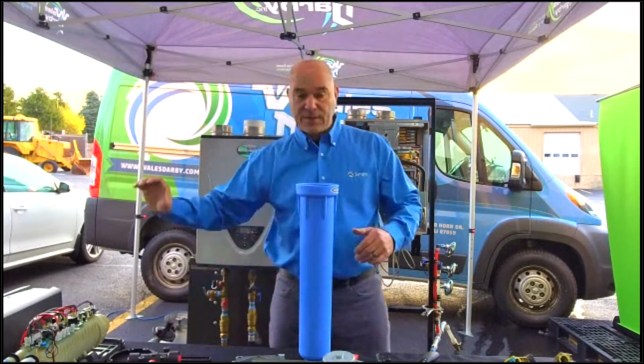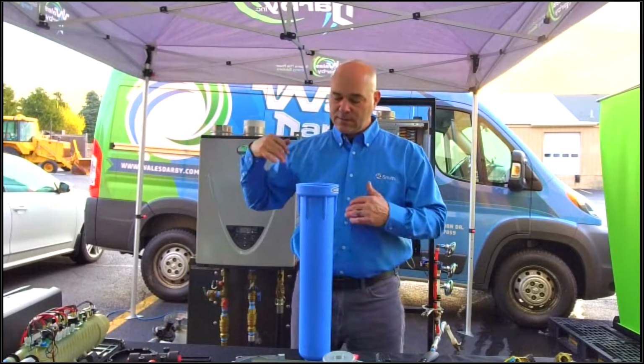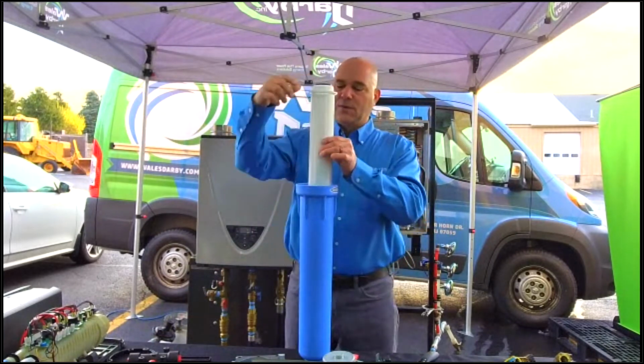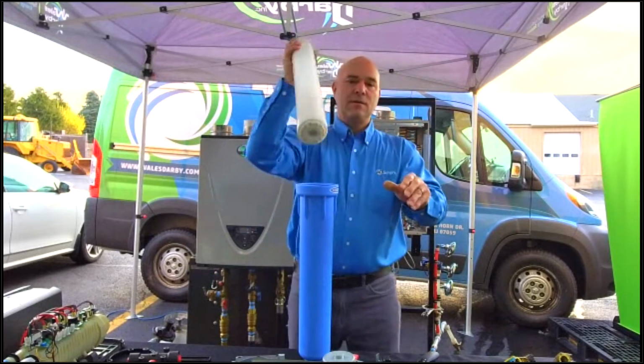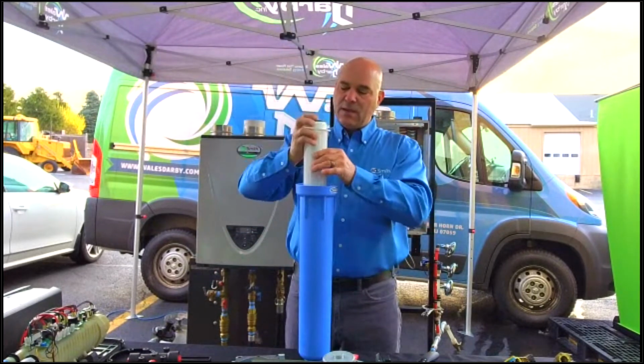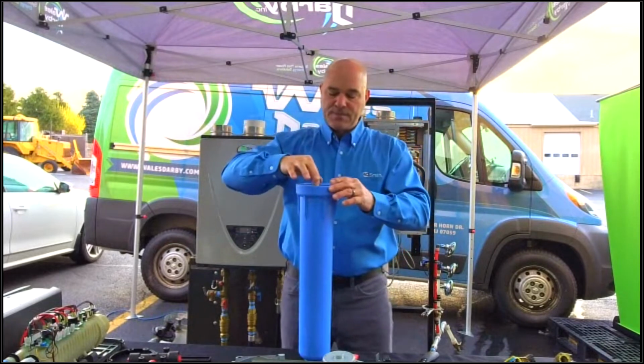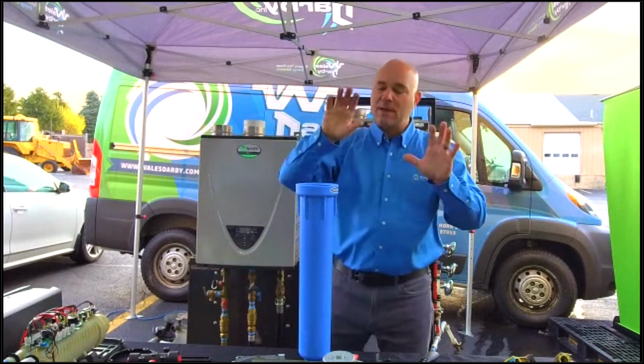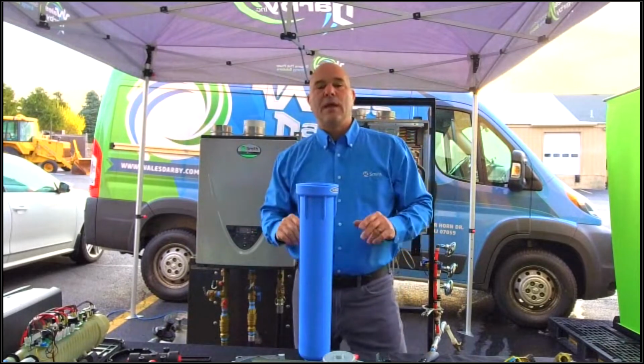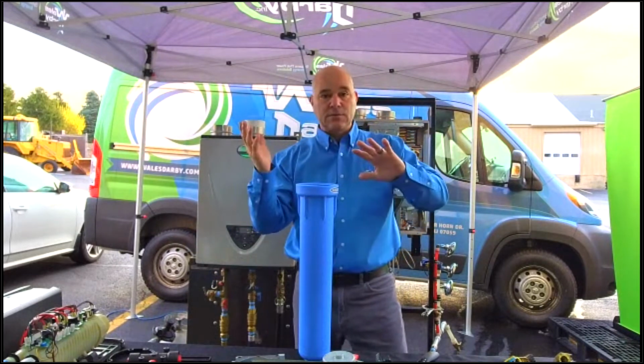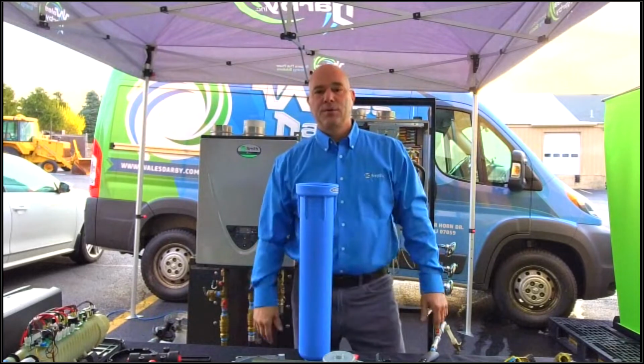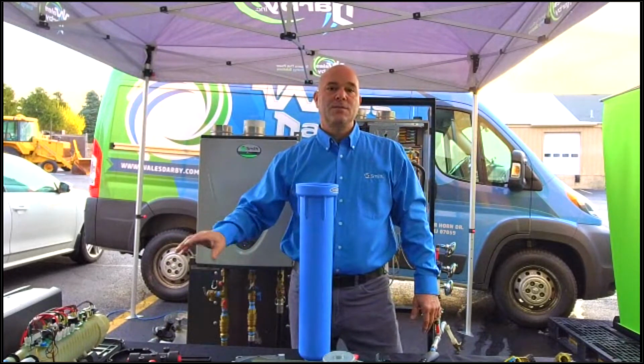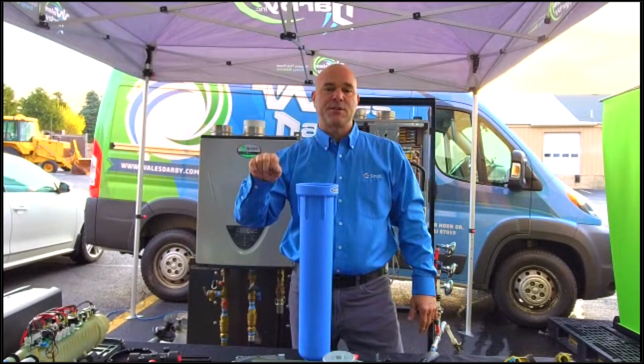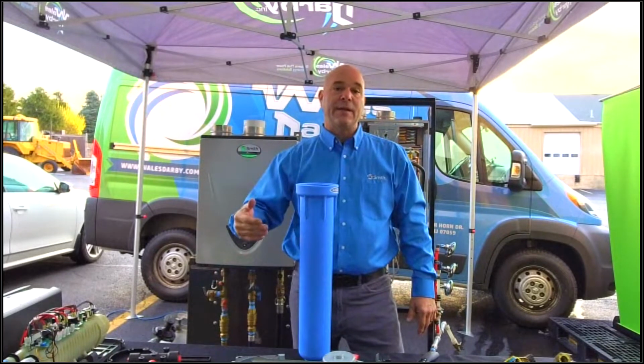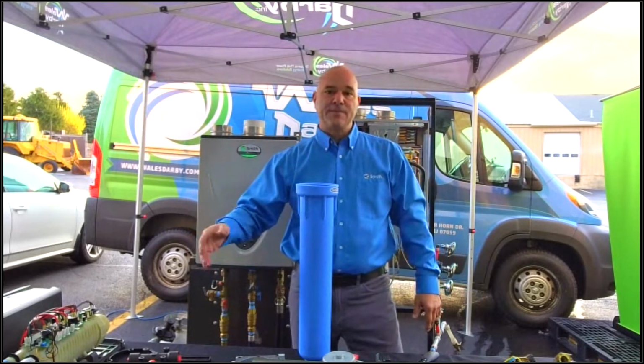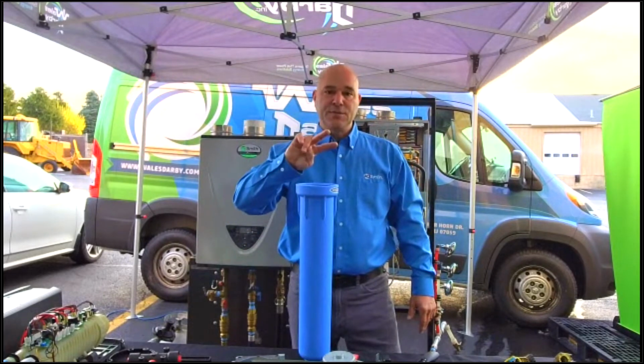And what we do is we put this on the cold water main coming into the tankless unit. Goes through this. We've got a cartridge in there. Cartridge has a bed in there. And what that does is that'll take the hard crystals that are coming through, and it will trick the crystals, basically coat the crystals, and allow them to pass directly through a tankless water heater. So they're not going to attach themselves to the heat exchanger, create hot spots in the heat exchanger, and create a heat exchanger failure. This will be good for 2 years.